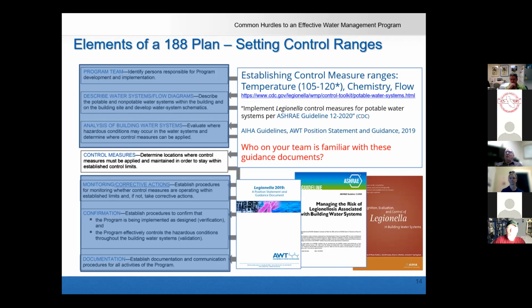The other thing you can do is look at a capital improvement, like putting thermal mixing valves on the floor so you can increase the heat getting to that floor and make it more stable. We see that a lot in high rises, where by the 6th floor, the temperature at the distal fixture is significantly different than near the 1st floor. If you try to get it hot at the distal end up high, you'll burn somebody on the 1st floor. So if you can get capital projects to put in a thermal mixing valve down the road, you can start increasing that circulating temperature.